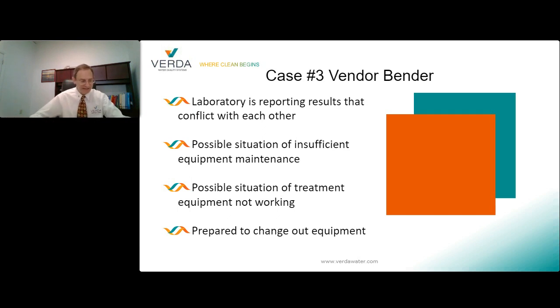So what does that mean, I asked? Well, it means we did everything correctly and the hardness reading is accurate. Now I explained to them that either the hardness reading was incorrect or the conductivity reading was incorrect. And they said, no, the conductivity test, we did that correctly as well. So I said, well, how do you explain this obvious contradiction? Like, yeah, I see your point, but I stand behind our laboratory's results, and I'm happy to state in front of the hospital committee this fact. So that's not very helpful. So the solution to the problem was to test the water with a different laboratory, which we did. And it, of course, indicated a much lower hardness. It was actually 0.5.